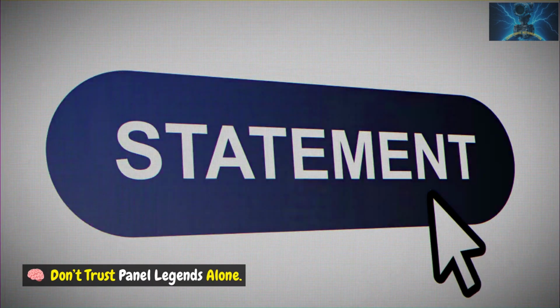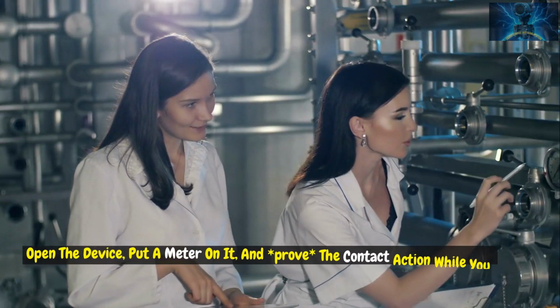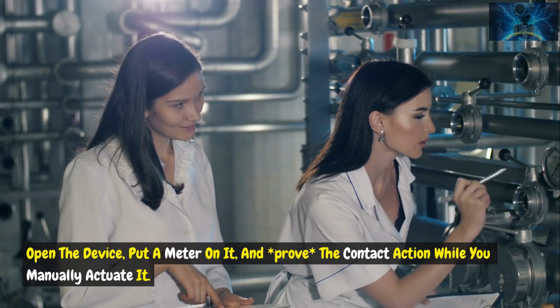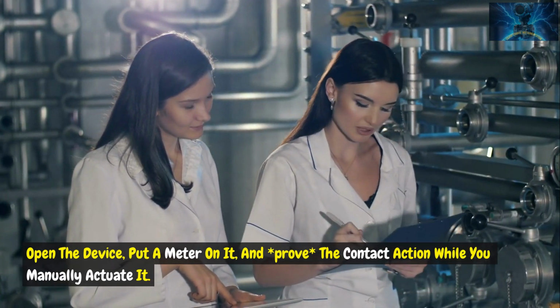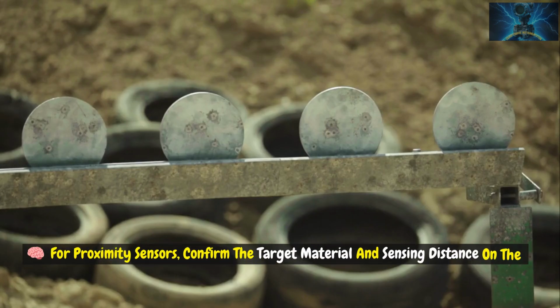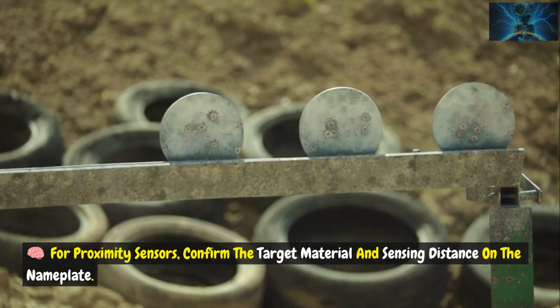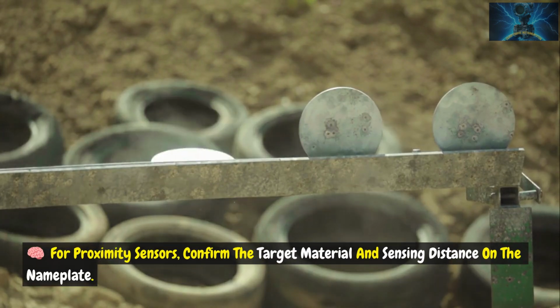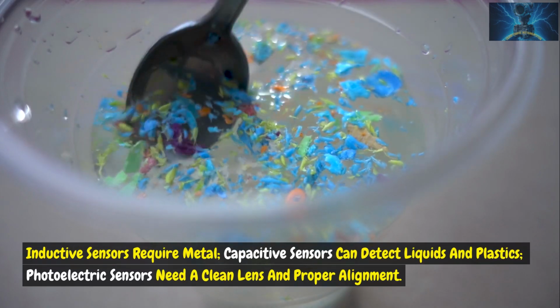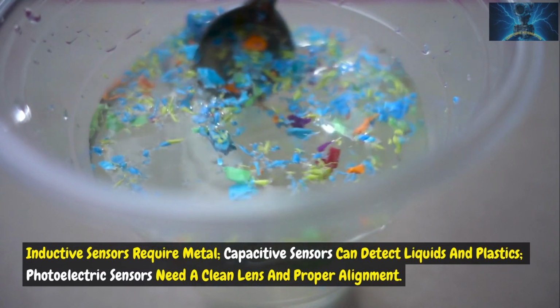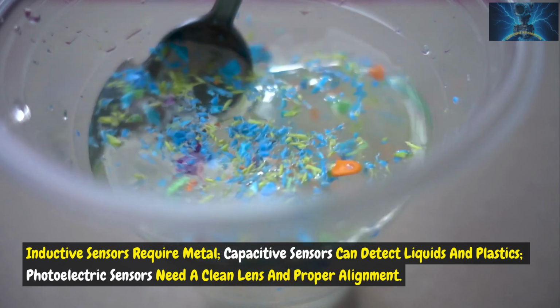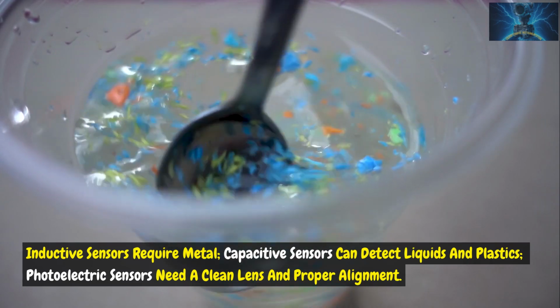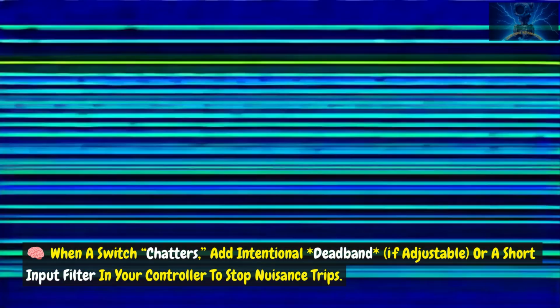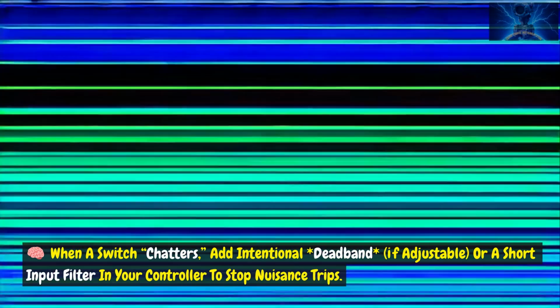Don't trust panel legends alone. Open the device, put a meter on it, and prove the contact action while you manually actuate it. For proximity sensors, confirm the target material and sensing distance on the nameplate. Inductive sensors require metal. Capacitive sensors can detect liquids and plastics. Photoelectric sensors need a clean lens and proper alignment. When a switch chatters, add intentional deadband, if adjustable, or a short input filter in your controller to stop nuisance trips.